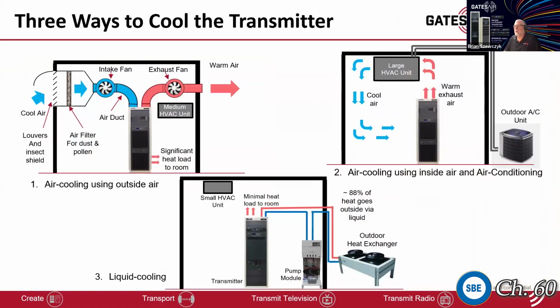So there's basically 3 ways of cooling a transmitter site. We can take outside air and bring it in. You want to have it filtered, and then have an exhaust fan to exit that air. That's one way of doing that. Another way of doing that would obviously be a closed loop system with an air conditioning system. This, I think, is much better. It keeps dirt and contaminants out. This technology using outside air, it can be very efficient in some locales. In other places, it can be very dangerous and damaging.